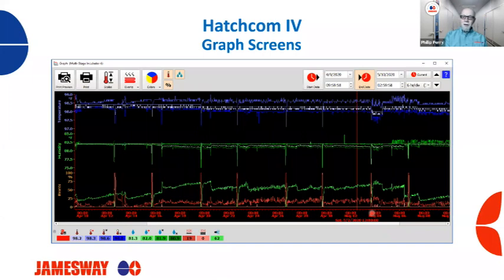So this heater element was staying on and driving our damper open, which meant we were losing our humidity. And so the nozzles were staying on. Again, just a multitude of problems occurring because that one heater bar was staying on. Because it was staying on, we were having these temperature swings and we were seeing some primary heat activity as well.